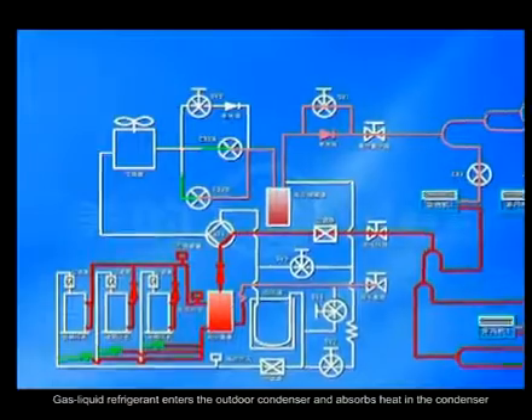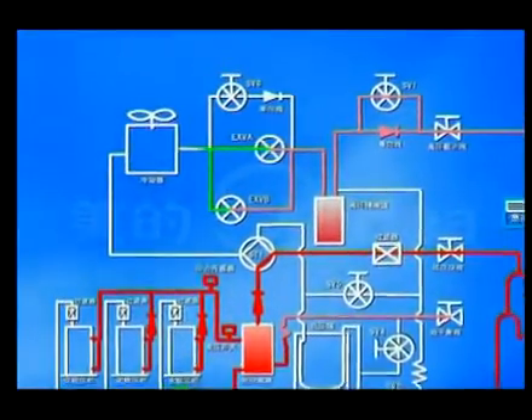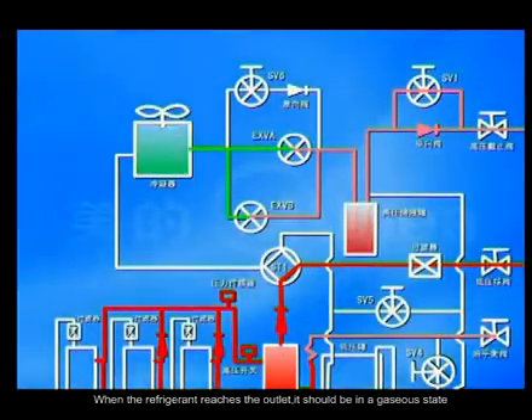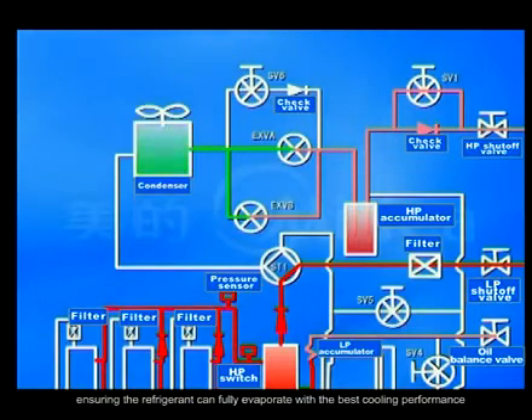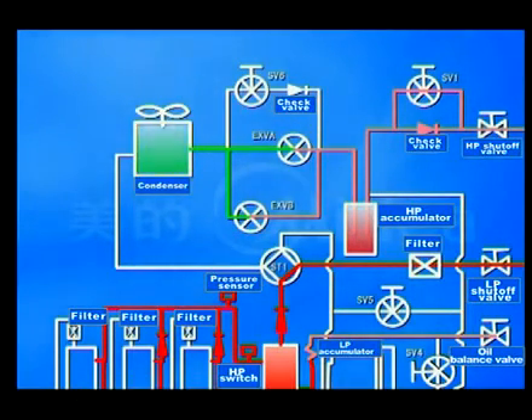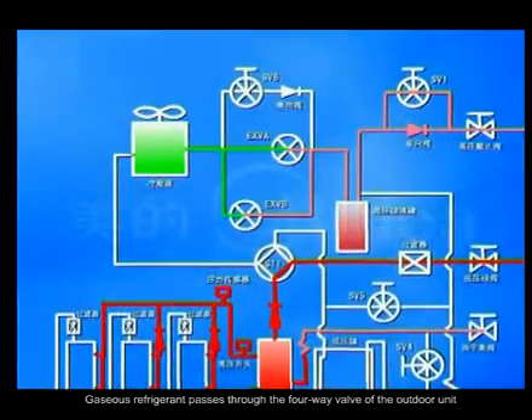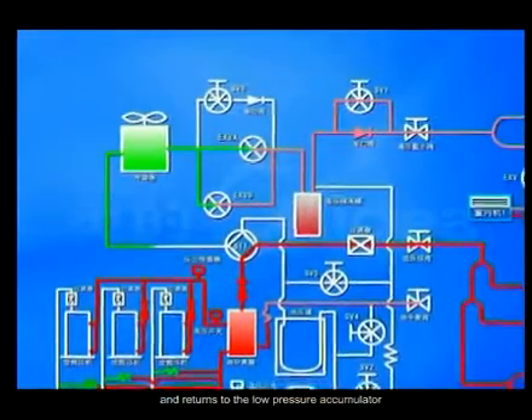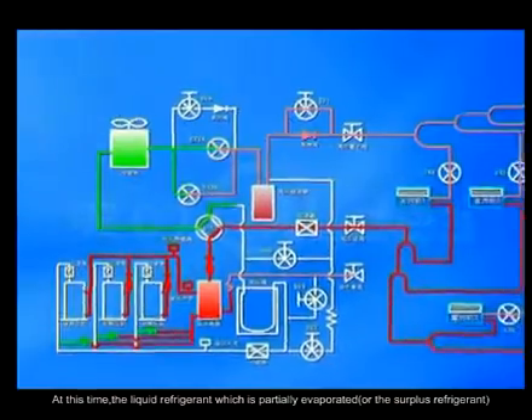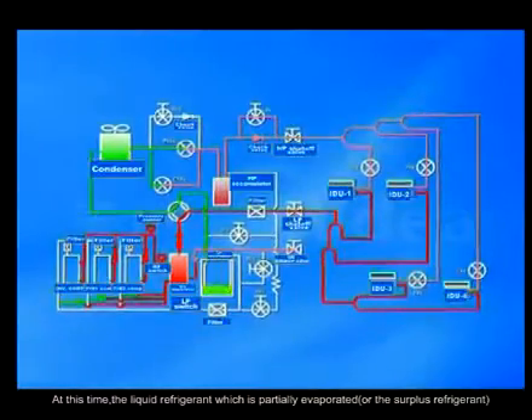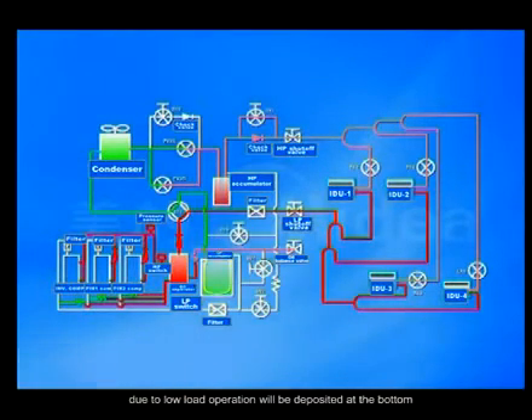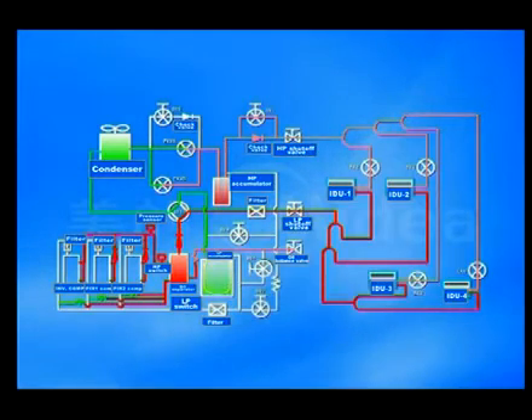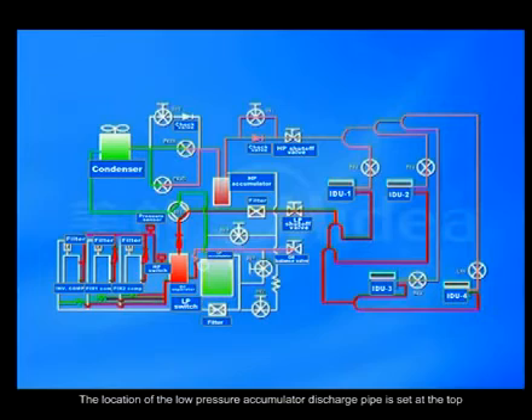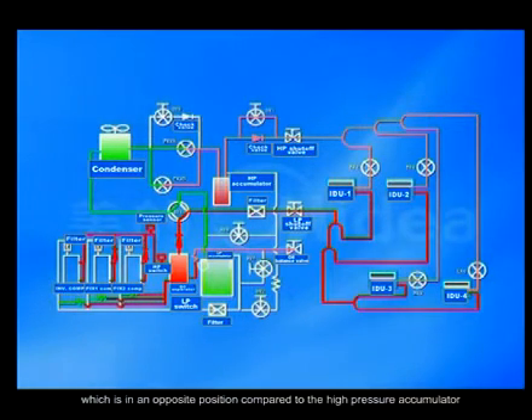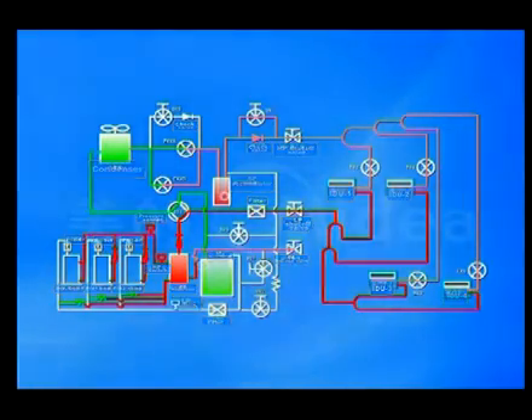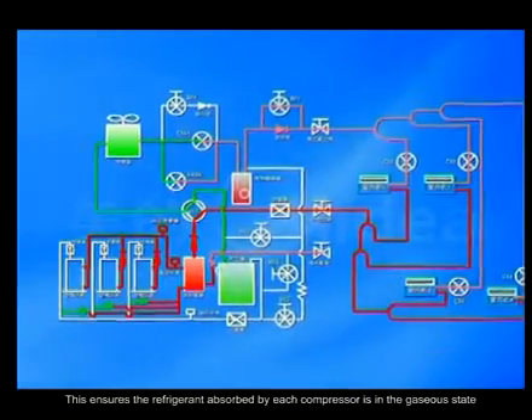Gas-liquid refrigerant enters the outdoor condenser and absorbs heat in the condenser. When the refrigerant reaches the outlet, it should be in a gaseous state, ensuring the refrigerant can fully evaporate with the best cooling performance. Gaseous refrigerant passes through the four-way valve of the outdoor unit and returns to the low-pressure accumulator. At this time, the liquid refrigerant, which is partially evaporated, or the surplus refrigerant due to low load operation, will be deposited at the bottom of the accumulator while the gaseous refrigerant remains at the top. The location of the low-pressure accumulator discharge pipe is set at the top, which is in an opposite position compared to the high-pressure accumulator.